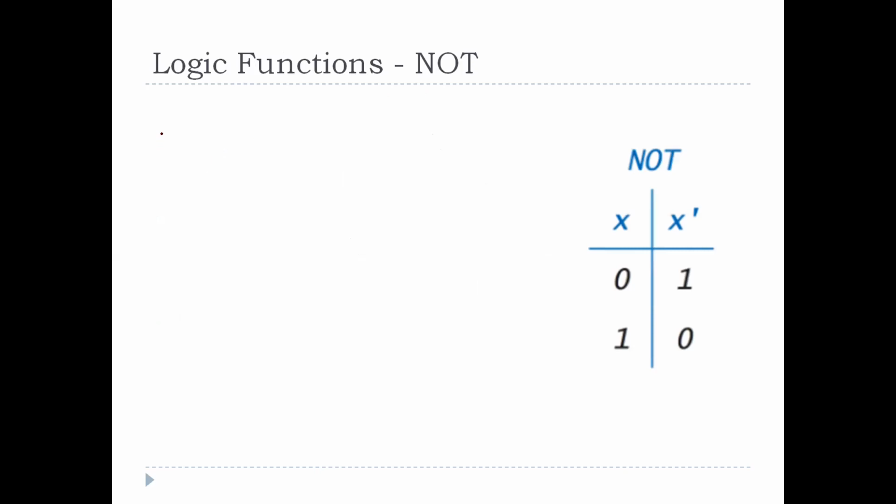For the NOT gate, the logic is that when input is 0, output should be 1. When the input is 1, output should be 0. It's very simple. It's a normally closed switch connected to the output. We'll mention the address for this as X400. This is Y430. Now when the input is 0, it will still be closed, so the output will be 1. When the input becomes 1, this will change its state. That is, it will become a normally open contact and hence the output will become 0.